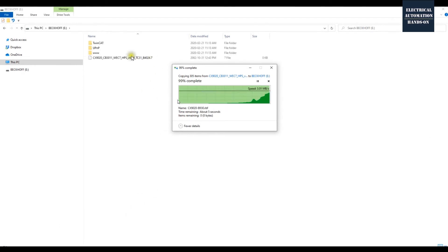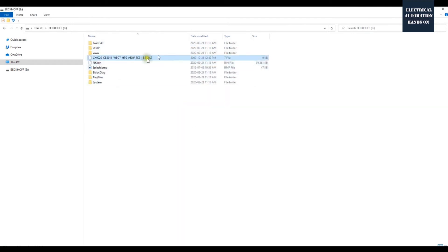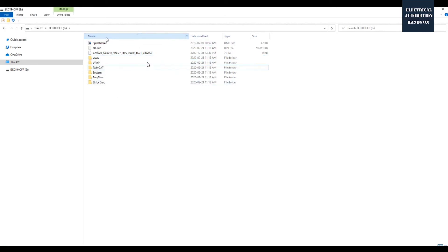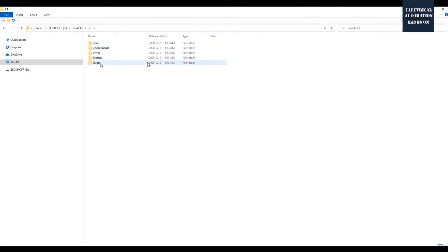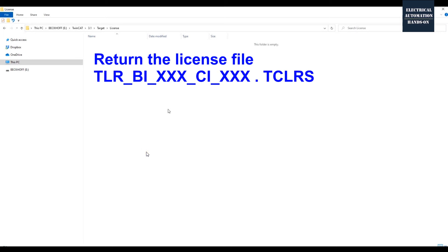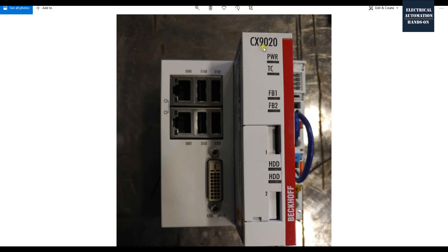Double-check that the version you copied to the micro SD is version 4024, the latest version. Then go back to the TwinCAT 3.1 target license folder and copy your backup license file back to the micro SD. Close the window and unplug the micro SD. Insert the card back into the controller — make sure to use slot number one, which is the system slot. Then connect power to the controller, and optionally connect the HMI screen so you can monitor the status and verify the firmware version after the upgrade.